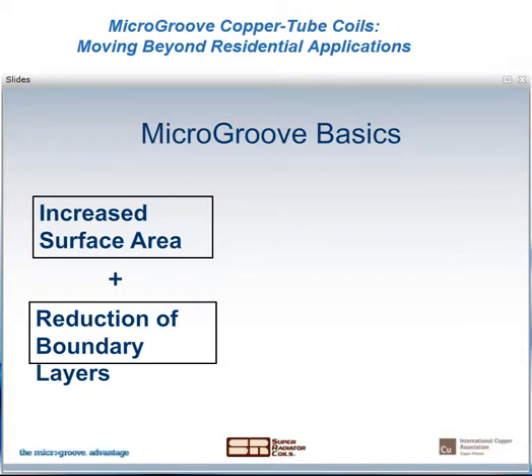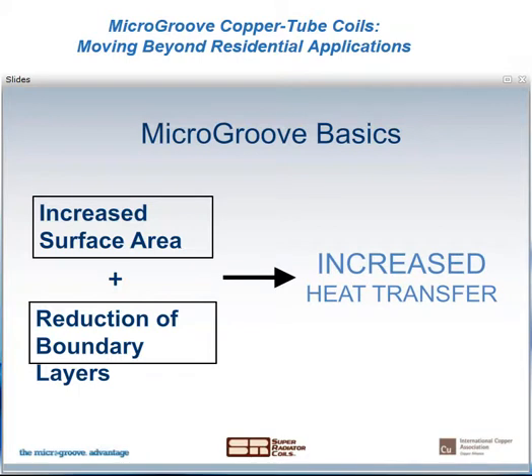So the two main phenomena that drive the benefits of MicroGroove technology are the increased surface area that we get from smaller tube diameters and the reduction of boundary layers both inside and outside of the tubes. And the result of increased surface area and reduced boundary layers is increased heat transfer. And what that really means for us is energy efficiency and potentially big cost savings. So let's look closer at using smaller diameter copper tubes because what on the surface looks like rather simple ideas, they can have pretty dramatic improvement on a cooling system, and it can get somewhat complex when it's time to decide just how these benefits will best be applied to a specific situation.